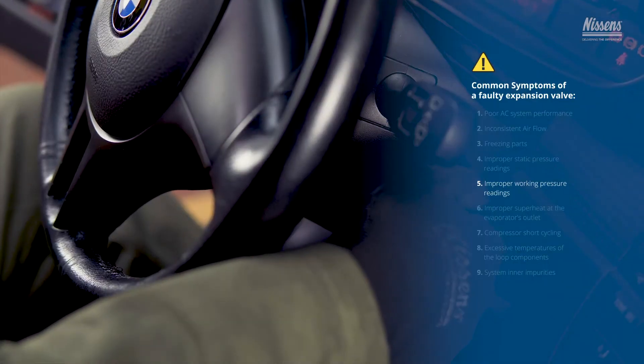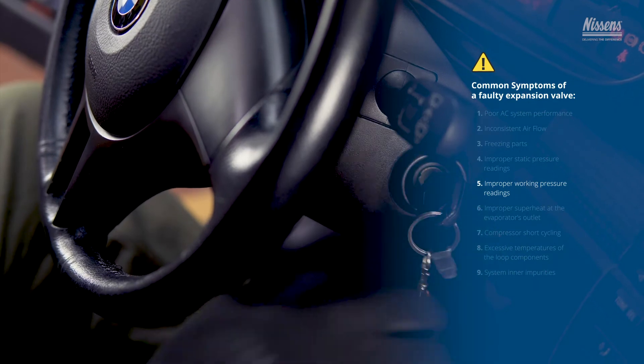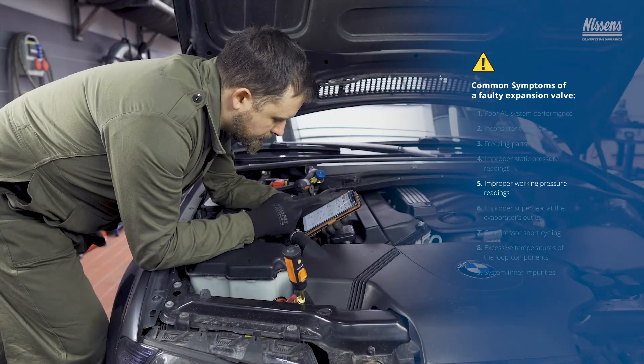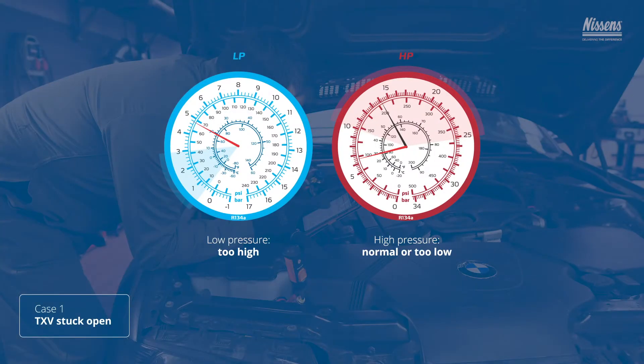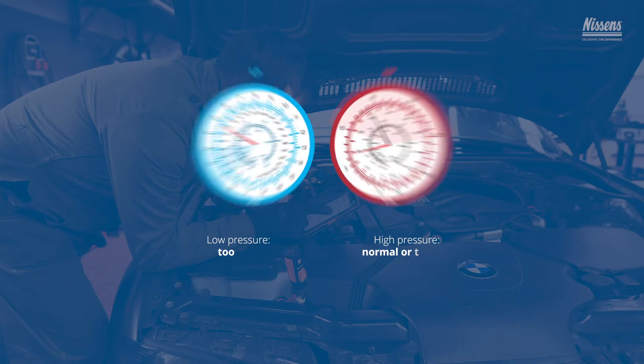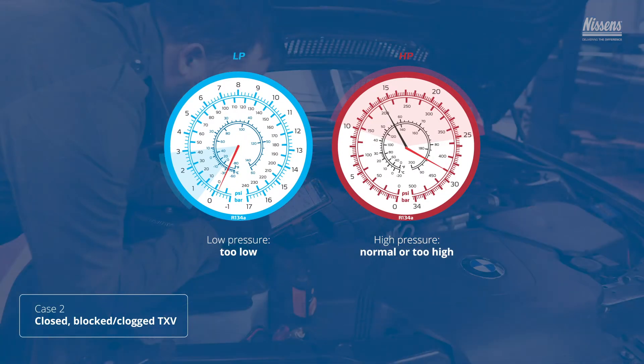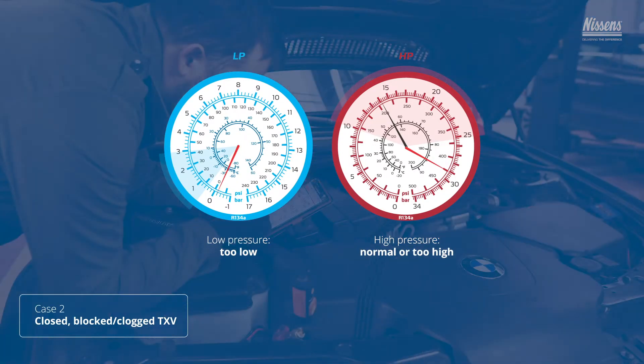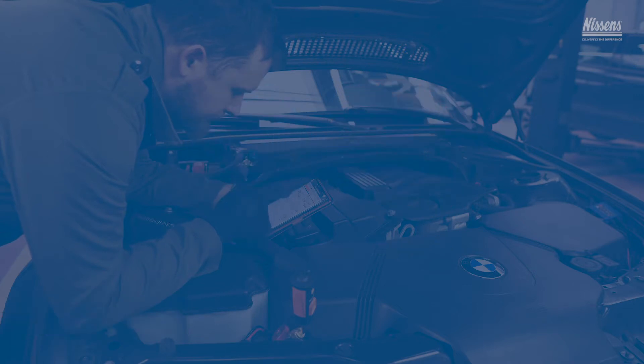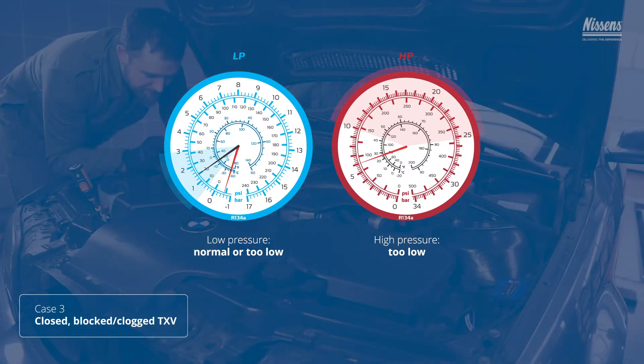Improper working pressure readings: depending on the system's design, too high or too low working pressure readings may be a sign of expansion valve malfunction. Normal gauge readings should be between 2 and 3 bar on the LP side and 14 to 24 bar on the HP side.